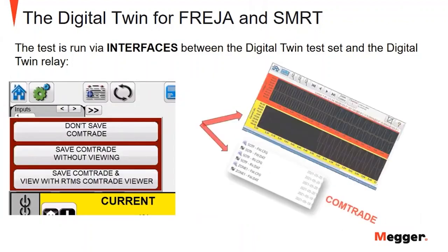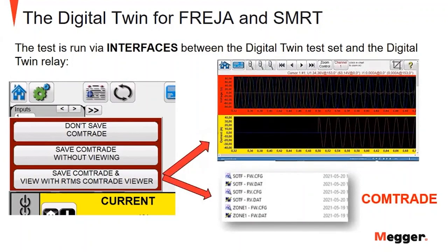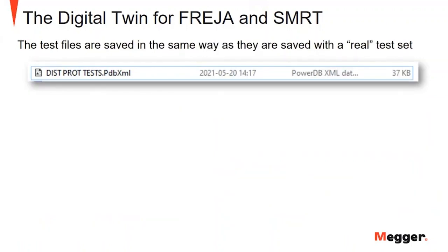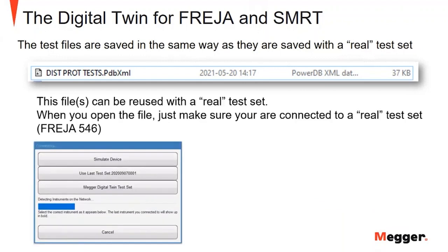And then we have done some user-friendly features. You can verify the ComTrade file in case you have done the wrong sequence, you have done some wrong values, etc. Or you just save it in ComTrade. But you are not saving as ComTrade. You are running the test, the digital twin runs, and the output is ComTrade. So the test file is saved in the normal way. It's a PowerDB XML file. So this file generated the ComTrade later on, but it's not important now.